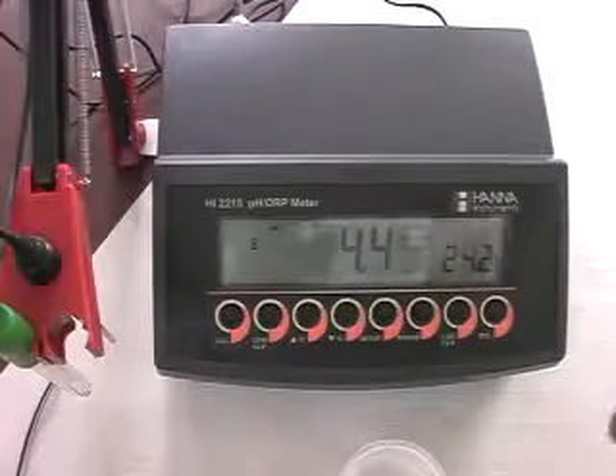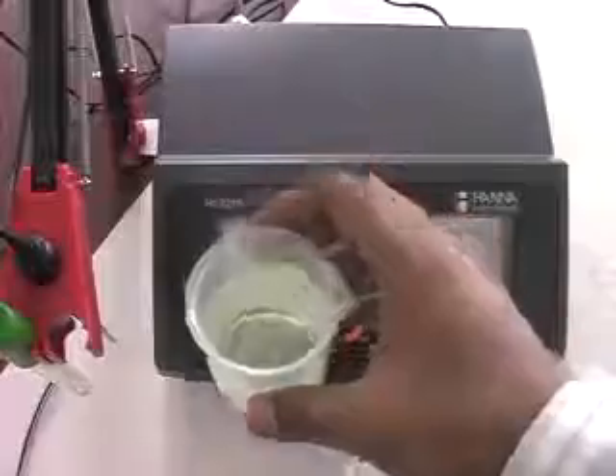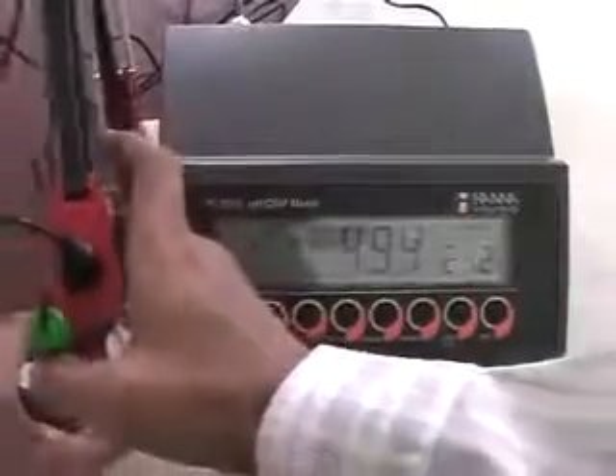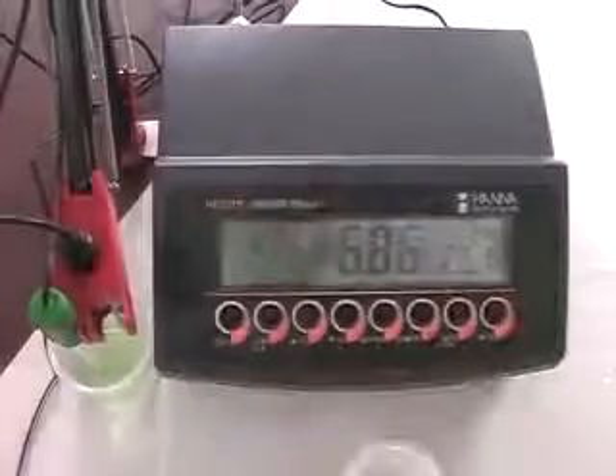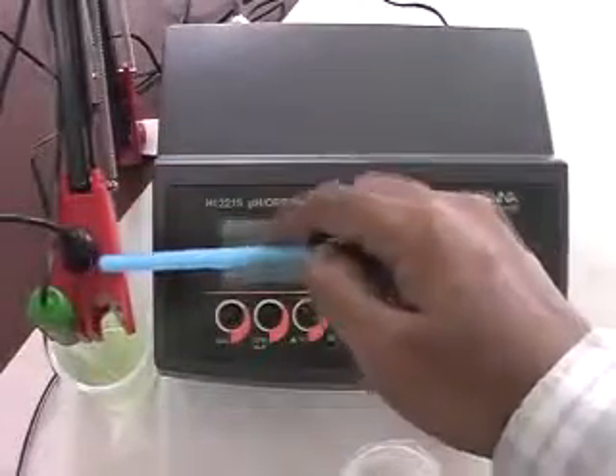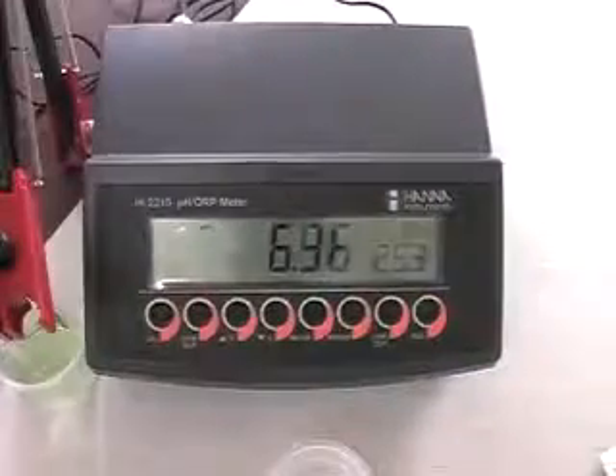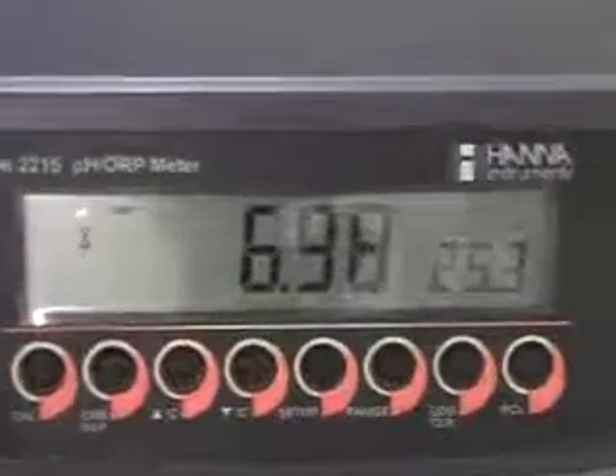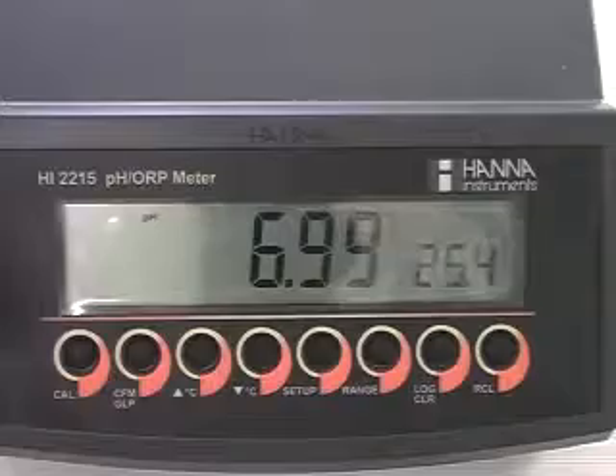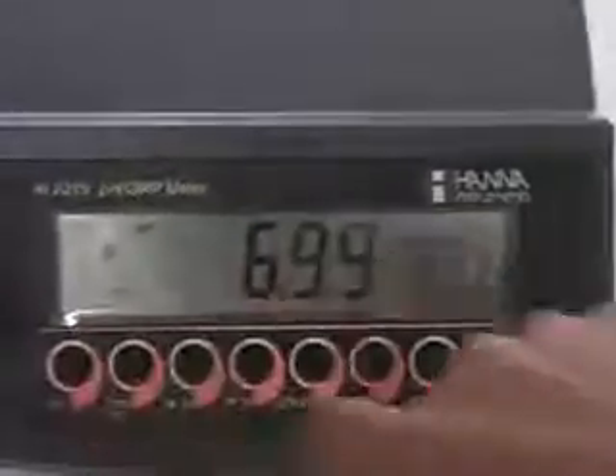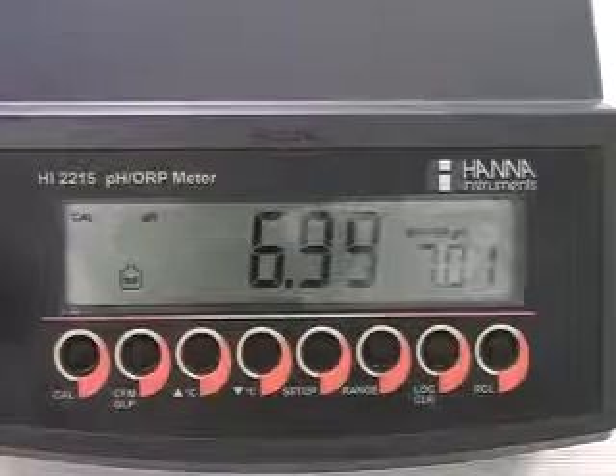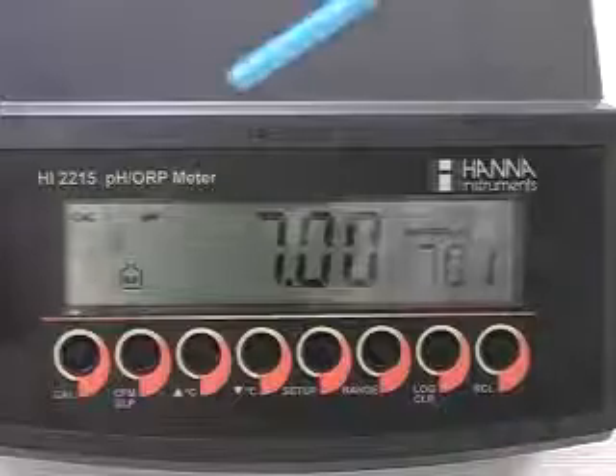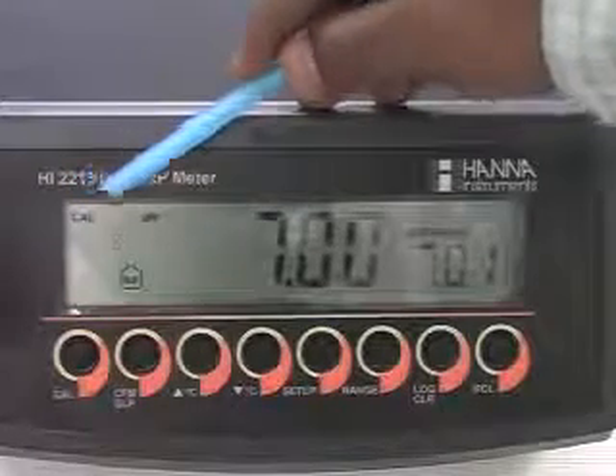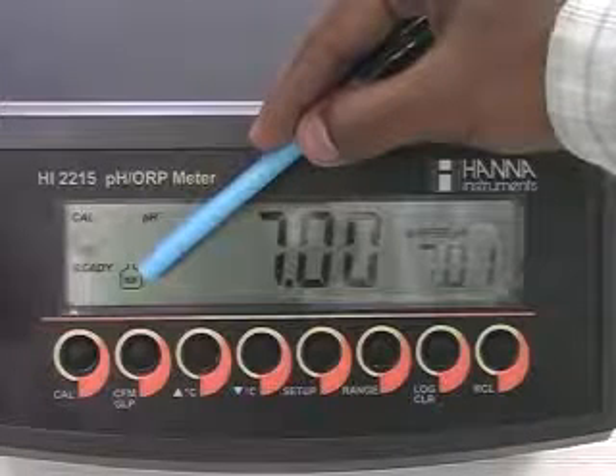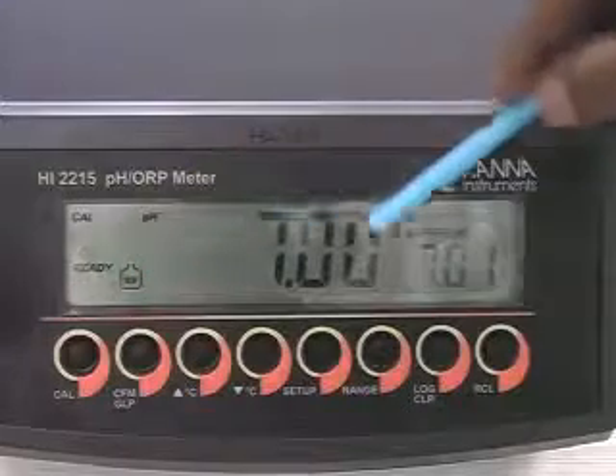Then submerge the pH electrode and temperature probe into the 7 pH buffer solution. The temperature probe should be close to the pH electrode. Now press the CAL key to enter into the calibration mode. The CAL and buffer tag will appear on the display and the 7.01 will display on the secondary LCD.